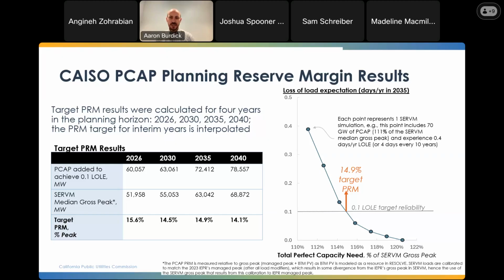The curve represents how much installed capacity you have versus the loss of load expectation measured in days per year. So if we want to meet the CPUC's 1 day in 10 target reliability standard, we'll draw a line on this curve at 0.1 days per year, or 1 day every 10 years, and then look at how much capacity is installed to determine the planning reserve margin.